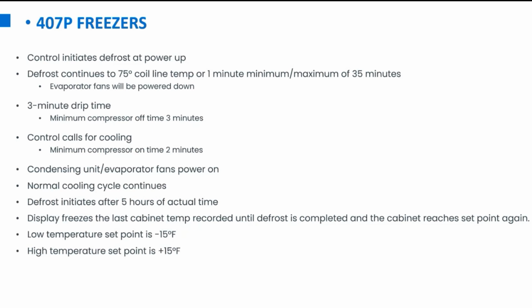So we'll go through defrost. The defrost can last anywhere from a minute up to around 35 minutes. We're looking for a 75-degree line temp on those as far as coil temp goes. So that hot gas defrost works really well. That will keep the lines nice and warm. So under normal operation on those, a typical defrost is probably going to be in that 10 to 15-minute range, assuming everything's operating normally on that.